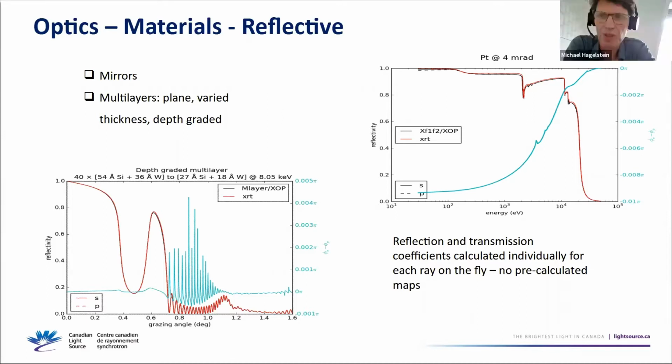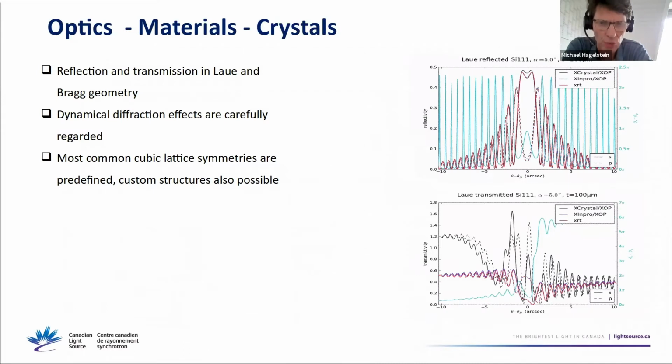Yeah, it would be actually good to have that feature in a double crystal monochromator, since when you do X-ray absorption spectroscopy, what you find very often is the intensity variations in your primary beam, say 111, but going through the diffraction condition, you observe from time to time strong changes in the intensity because there are other reciprocal lattice planes giving rise to some interference in the diffraction.